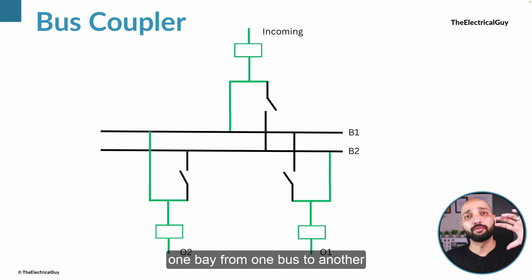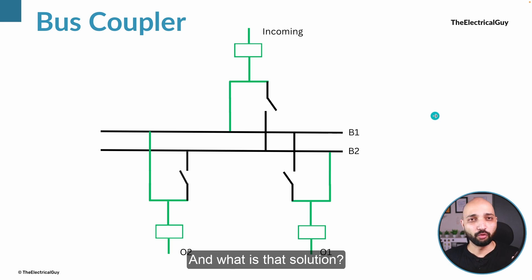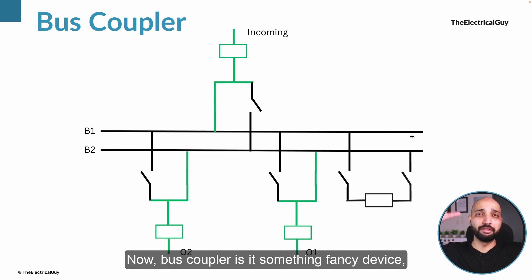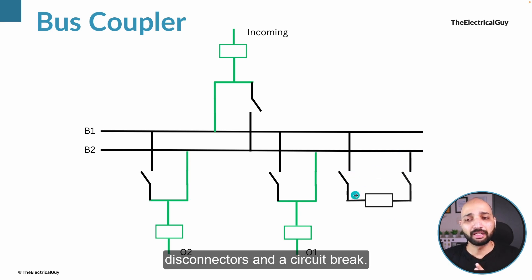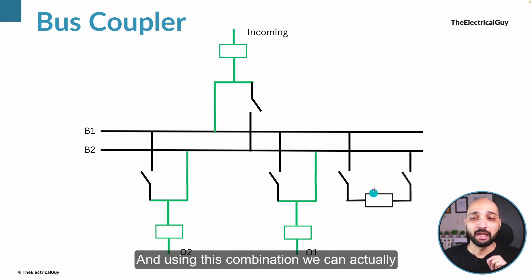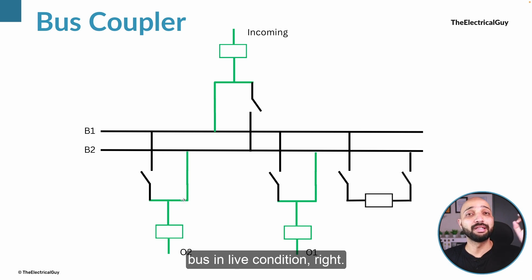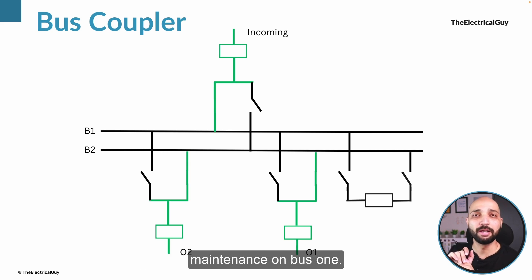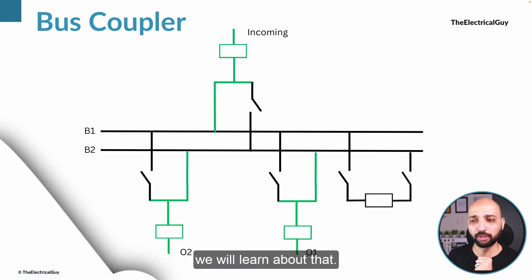There is a simple solution that lets you transfer one bay from one bus to another bus in live supply, without taking any shutdown — and that solution is the bus coupler. The bus coupler is not a fancy or complicated device; it is simply a combination of some disconnectors and a circuit breaker. Using this combination we can transfer one bay from one bus to another in live condition. Even if you need to carry out maintenance on bus one, you can transfer all the load to bus two and keep the system running.